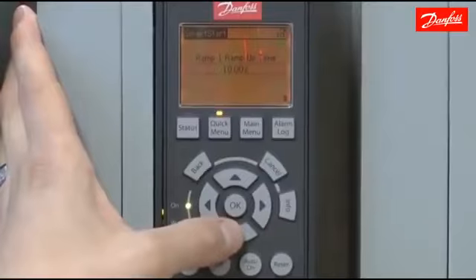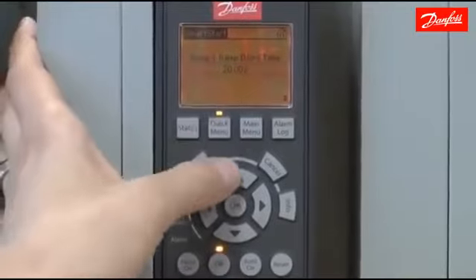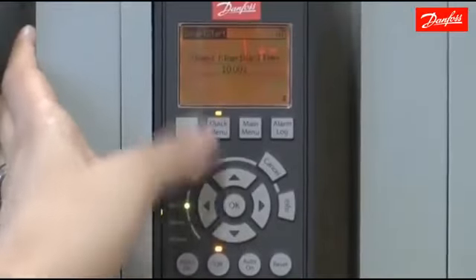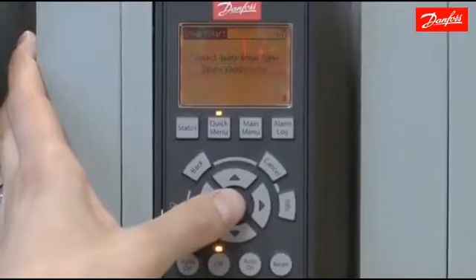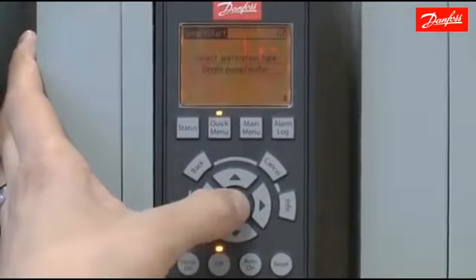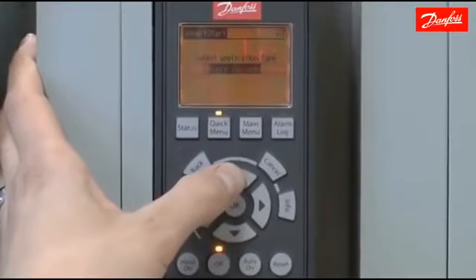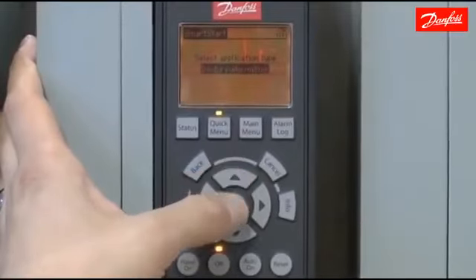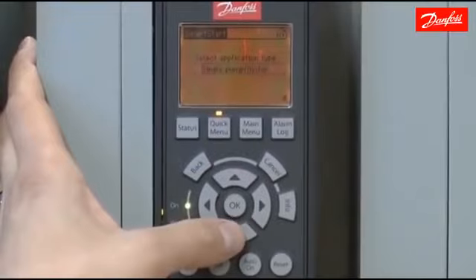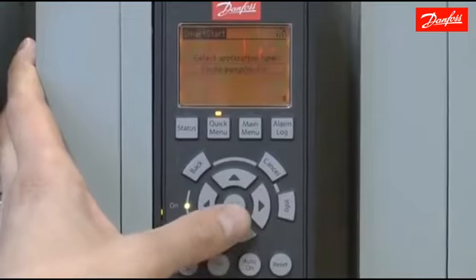Now we're going to move on to the pump ramp times. You can choose these, they're user defined of course, ramp up time and ramp down time. We'll leave the defaults of 10 seconds up and 20 seconds down for this example. The application type, we're going to be using a single pump or motor. I have other choices here where I can do basic cascade control, master follower, motor alternation.